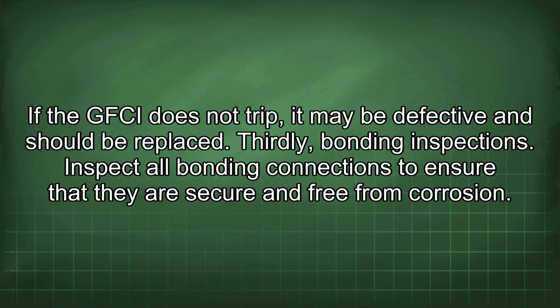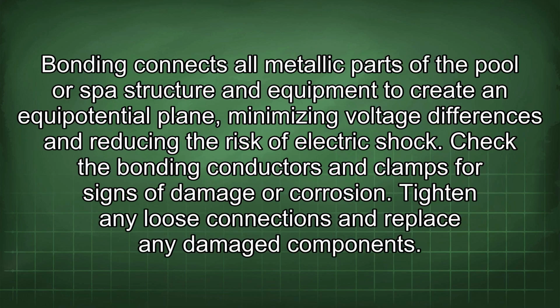Thirdly, bonding inspections. Inspect all bonding connections to ensure that they are secure and free from corrosion. Bonding connects all metallic parts of the pool or spa structure and equipment to create an equipotential plane, minimizing voltage differences and reducing the risk of electric shock. Check the bonding conductors and clamps for signs of damage or corrosion. Tighten any loose connections and replace any damaged components.